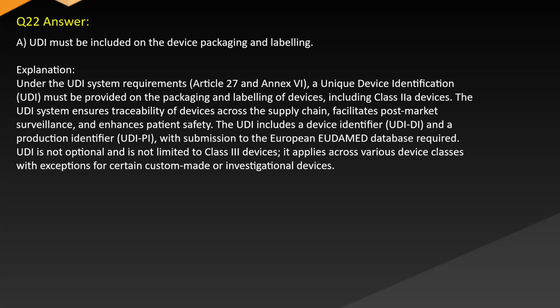The UDI includes a device identifier (UDI-DI) and a production identifier (UDI-PI), with submission to the European UDI database, EUDAMED, required. UDI is not optional and is not limited to Class III-only devices. It applies across various device classes, with exceptions for certain custom-made or investigational devices.